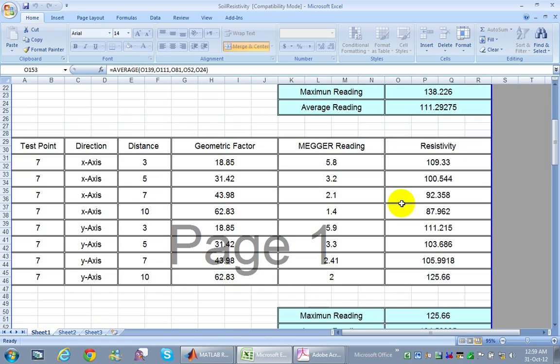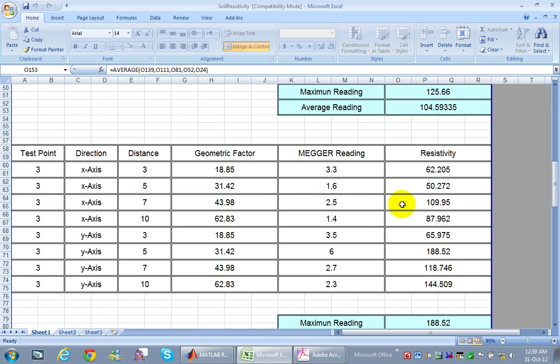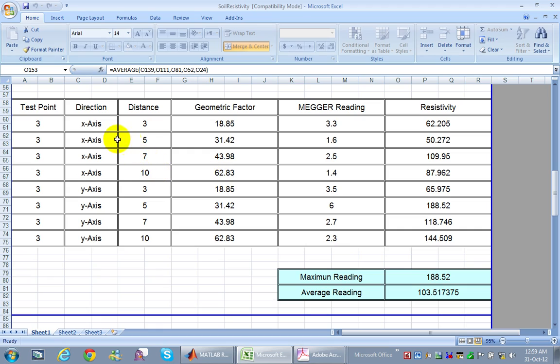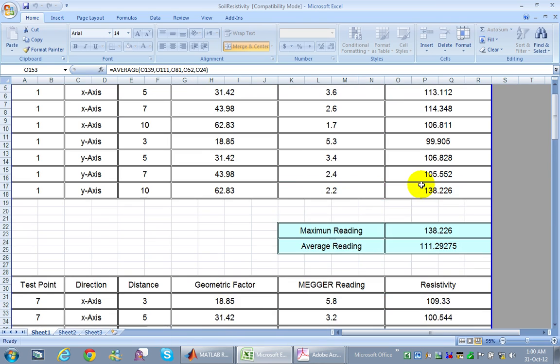However, changing the measurement location might show different results — for example, 62 ohm-meter at 3 meters but 144 ohm-meter at 10 meters. In this case we can conclude that the lower layer of the soil has higher resistivity than the upper one, so it is better to lay the grounding grid in the upper layer.